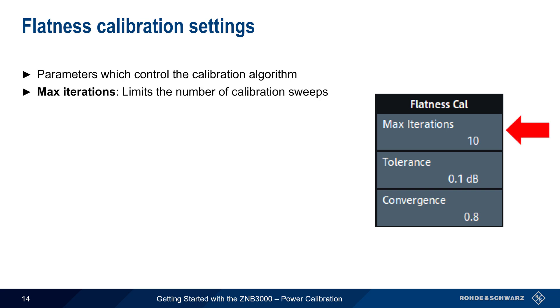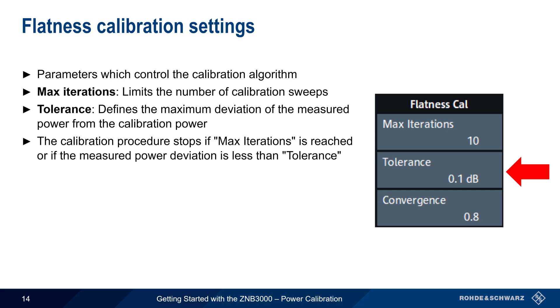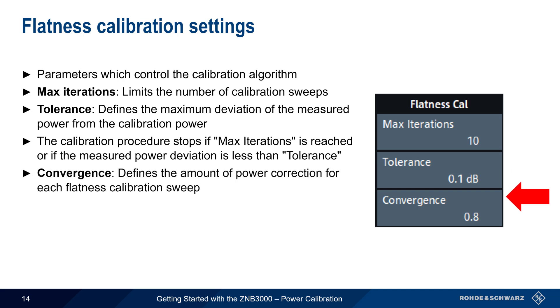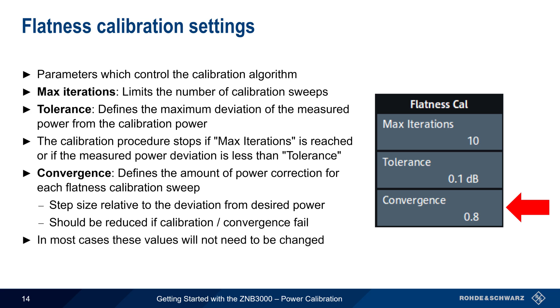The final set of configurable parameters are those for flatness calibration, which control the calibration algorithm. Max Iteration limits the number of calibration sweeps, and Tolerance defines the maximum allowable deviation of measured power from calibration power. The iterative routine stops once either max iterations is reached or the deviation is less than the tolerance value. Convergence defines the allowable change in power correction per flatness calibration sweep — specifically, the step size relative to the amount of deviation from the desired power level. This value should be reduced if calibration or convergence fails. In most cases, the default values will not need to be changed.